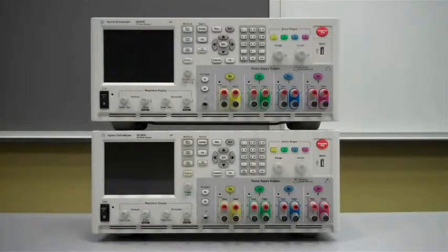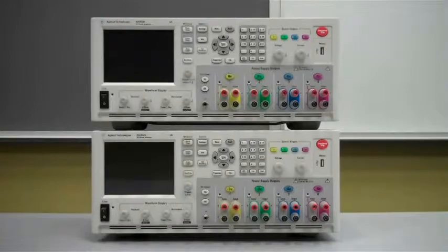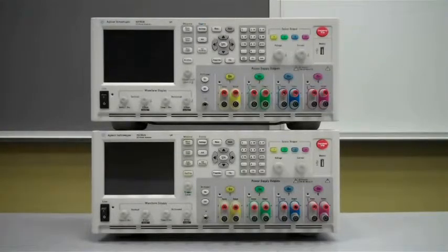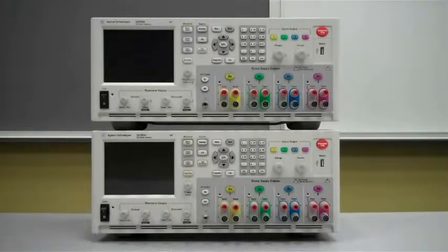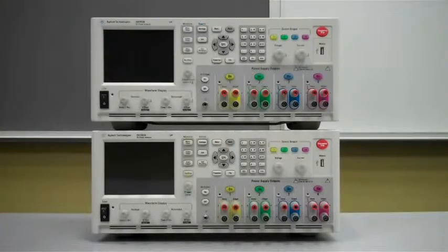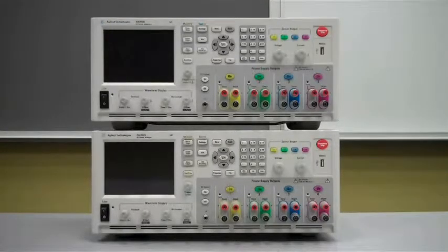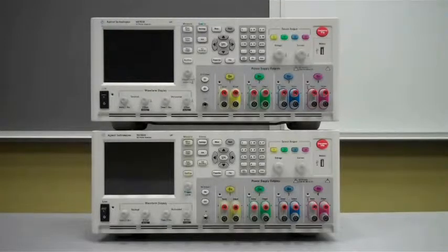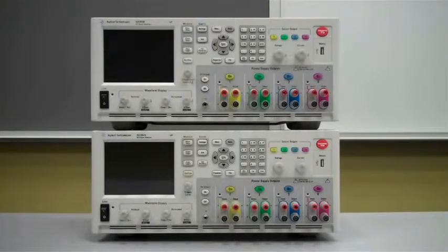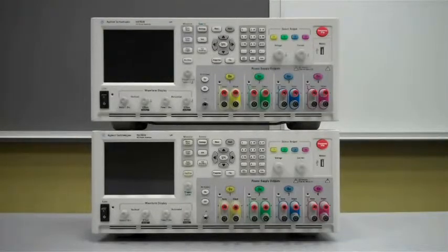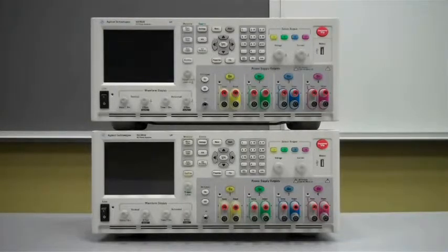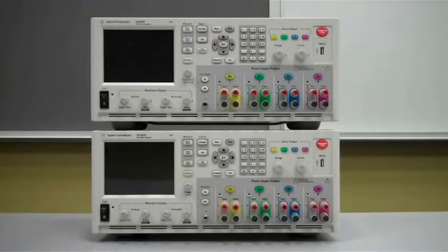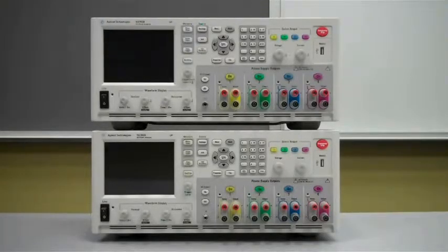The first thing we'd like to talk about are the modules that each unit supports. The B mainframe supports all the same modules as the A mainframe. In addition, the B mainframe will also be able to support the N6753A 20V 50A 300W module. Both mainframes can support the new N6780 SMU modules that are coming out.